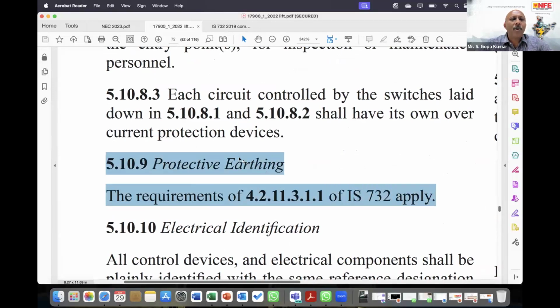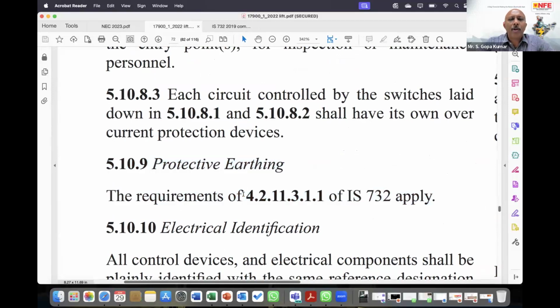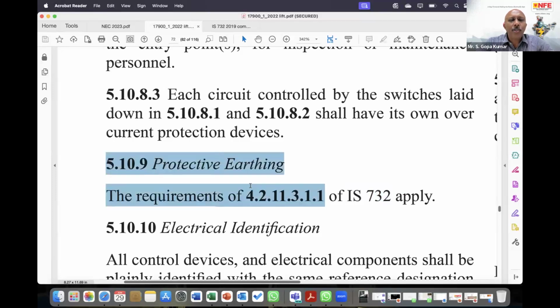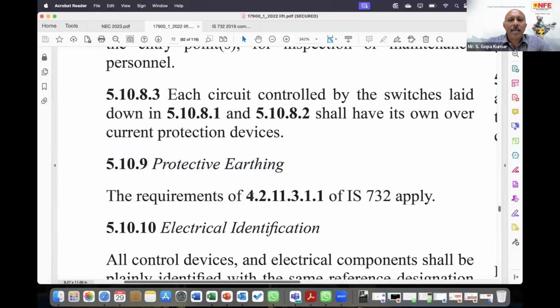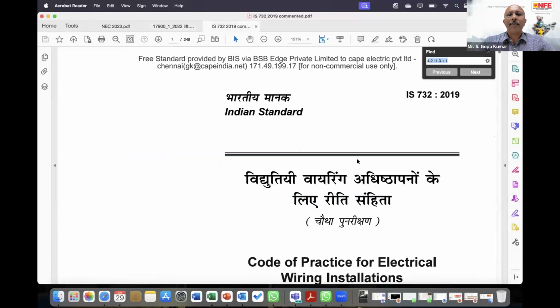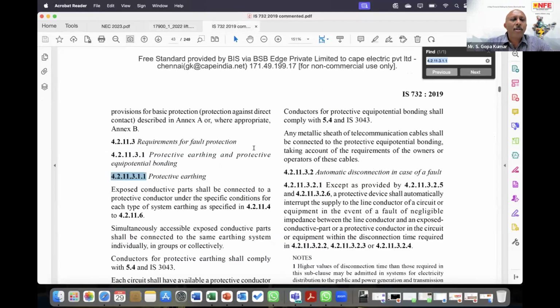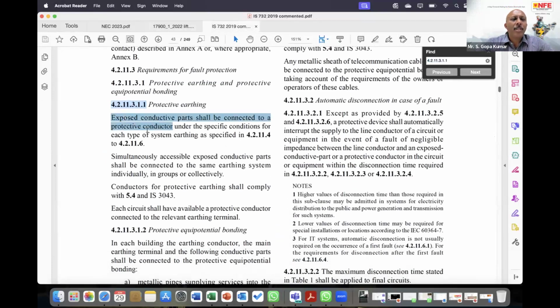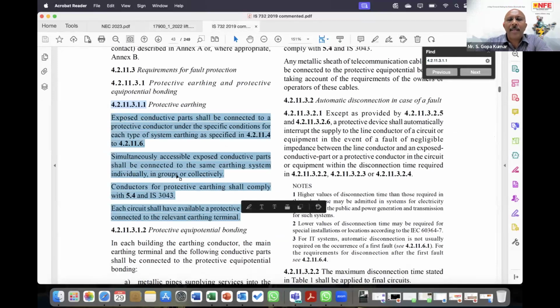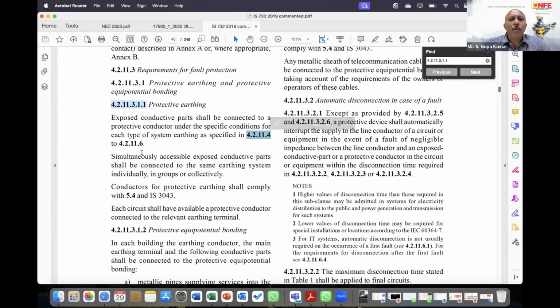So IS 17900 says you should follow the requirements of 4.2.11.3.1.1 of IS 732. Basically, this IS is derived from the ISO standard, ISO 8100. In the ISO standard, the respective clause of IEC 60364 is mentioned. So basically, this is the clause of IS 732. I also have IS 732 on my screen. I am showing you the clause on protective earthing. This clause explains how protective earthing for safety has to be carried out in a lift. Basically, it covers clauses 4.2.11.4 to 11.6. This talks about what we should do in a TN system, what we should do in a TT system, and what we should do in an IT system.